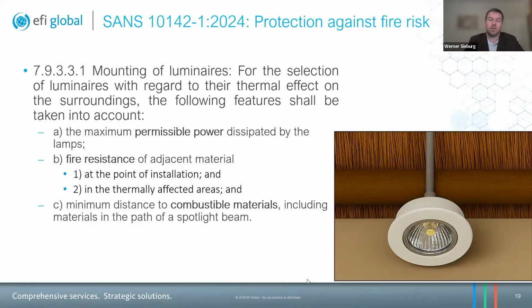And so if it was designed and installed in this manner, that would mean that the designer or the installer did not take into account, number A, the maximum permissible power dissipated by the lamps, right? And the corresponding heat that is generated by the lamp. And also the fire resistance of the adjacent material. In this context, for example, there's no fire resistant material at all between the lamp and the thatch. So at the point of installation and in the thermally affected areas. So this is basically the heat radiating upwards or towards the thatch from the lamp during operation.